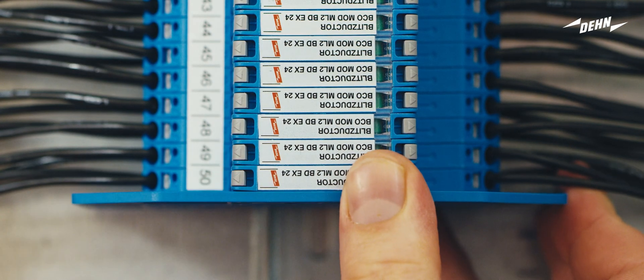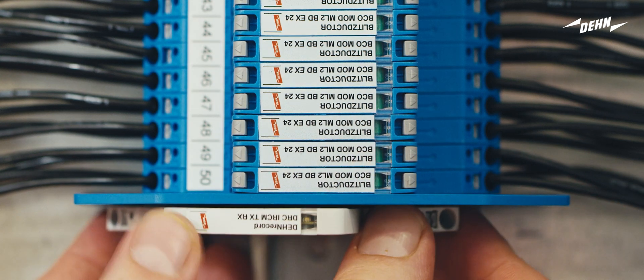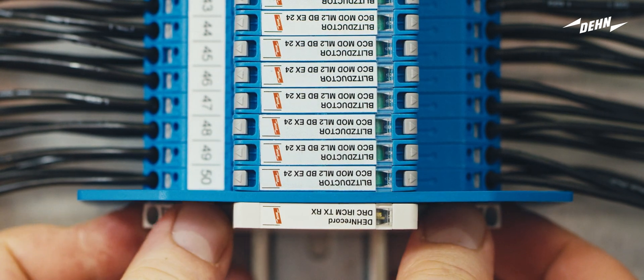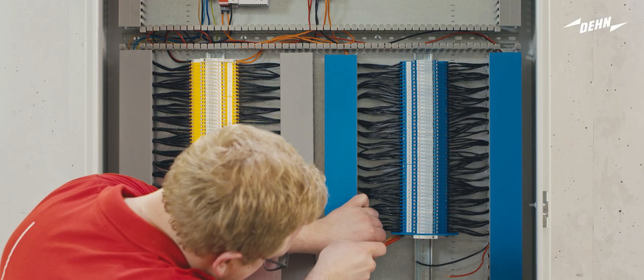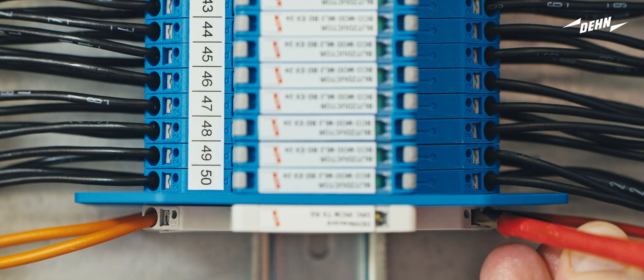Install the Ex(i) partition to maintain a distance of 50mm between the intrinsically safe and the non-intrinsically safe signal circuit.